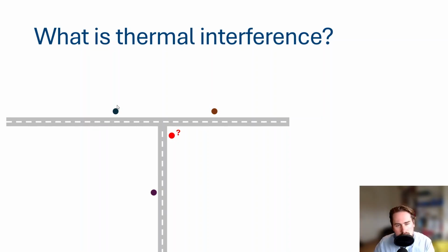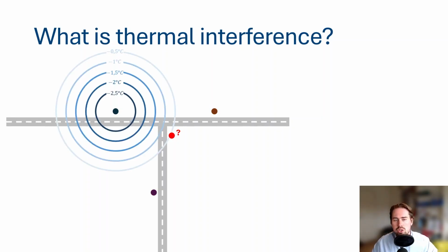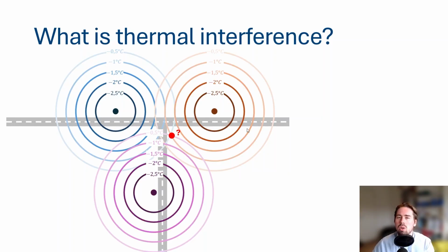And imagine that this left neighbor, this blue neighbor, has a project with a heating dominated building, and they extract more heat from the ground than they inject. So over the years, 25 years, the ground around this borehole will be cooled down because the heat has been extracted due to the imbalance. And the closer you are to this borehole, the lower the temperature will drop over time. But it's not only this blue borehole, also the borehole on the right and on the bottom can have the same behavior. Due to the imbalance, the ground will cool down around this borehole.